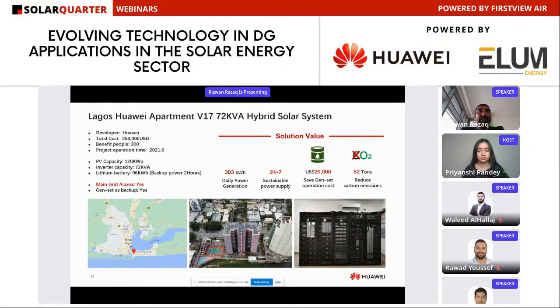Another project in Lagos, in an apartment building, where solar is only accessible from the rooftop area. So the system is a lot smaller, around 120 kilowatt peak, with an inverter capacity of around 72 kVA, and lithium ion batteries of around 96 kilowatt hours, with backup of up to 2 hours supply.